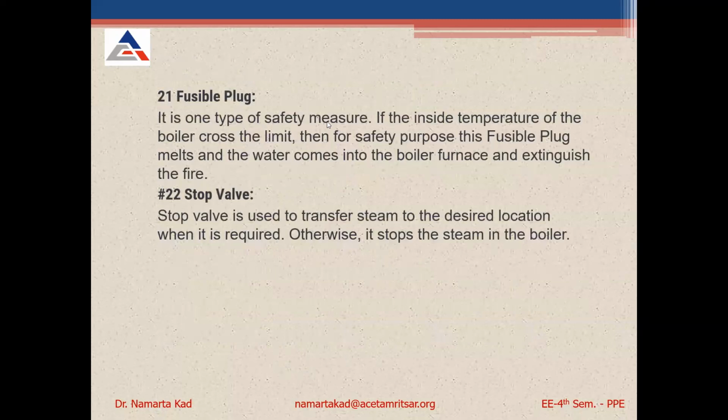Then the fusible plug is there. It is one type of safety measure. If the inside temperature of the boiler crosses the limit, then for safety purposes, this fusible plug melts. Okay, and the water comes into the boiler furnace and extinguishes the fire.